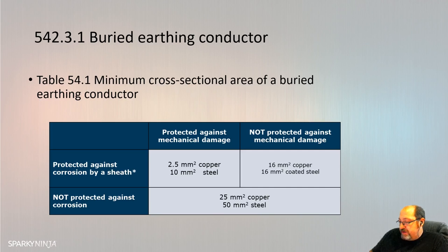For a tape or strip conductor, the thickness shall be such that it will withstand mechanical damage and corrosion. So we're not talking here about the effectiveness of the earthing conductor for an earth. We're talking about the consideration that taking an earthing conductor and burying it in the ground, it may require sizing to accommodate protection against mechanical damage and protection against corrosion. And that is given in this table.